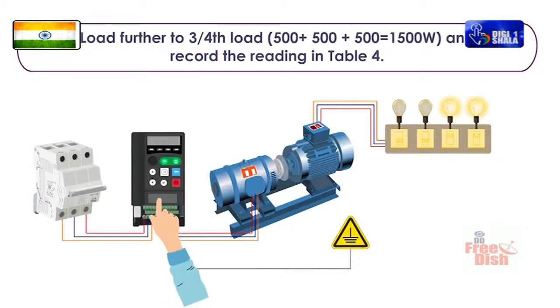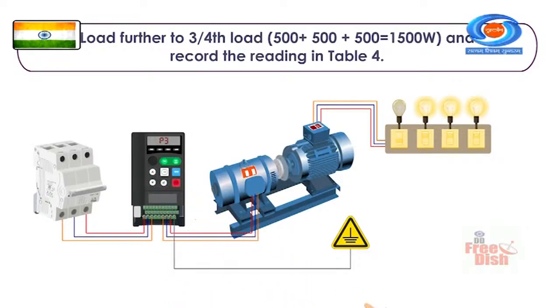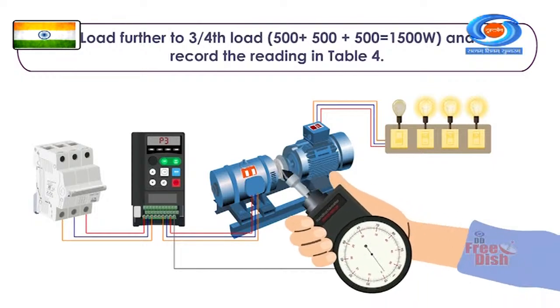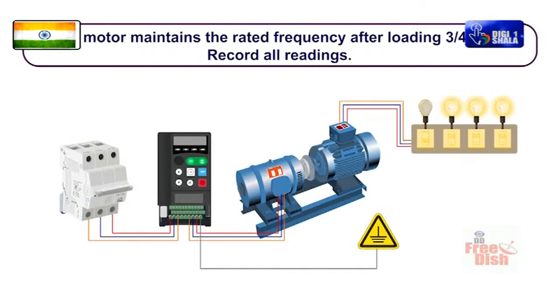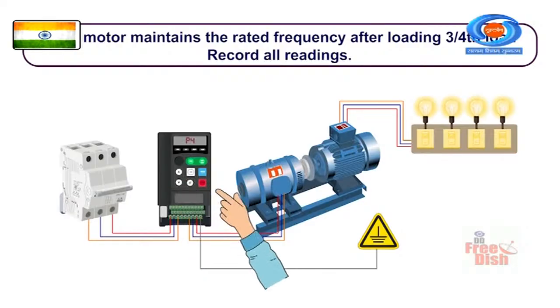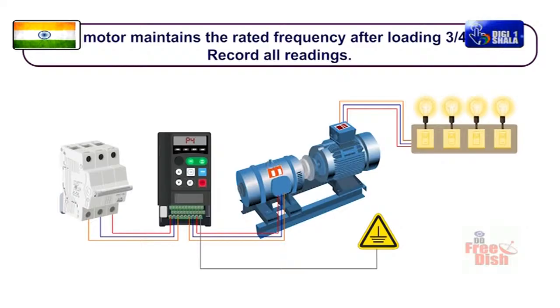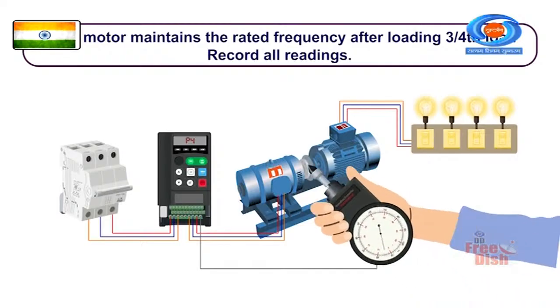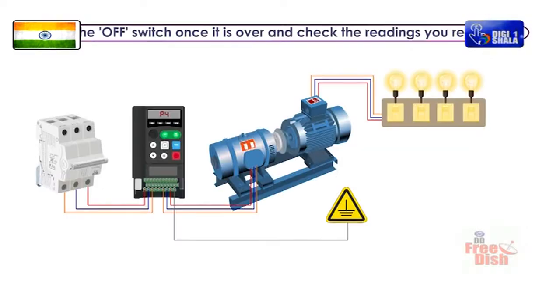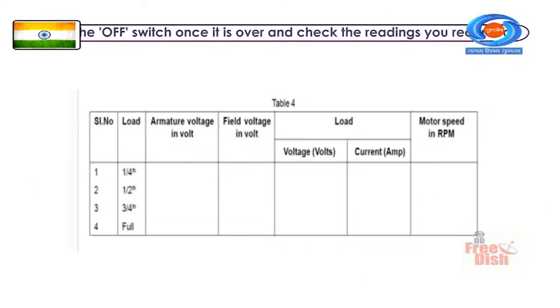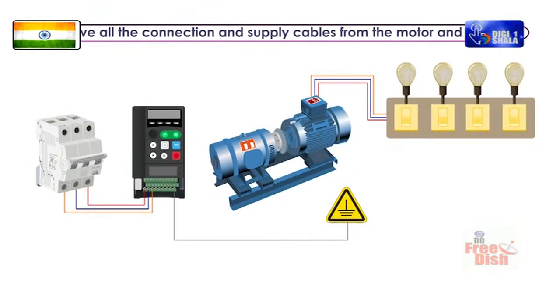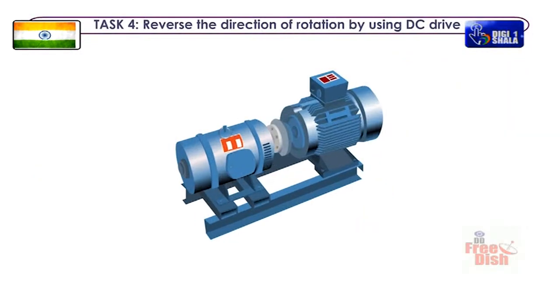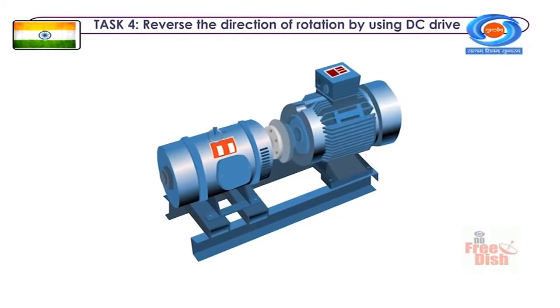Load further to 3/4 load, 500 plus 500 plus 500, which equals 1500 watt, and record the readings in Table 4. If the motor maintains the rated frequency after loading to 3/4 load, record all readings. Press the off switch once it is over and check the readings you recorded. Remove all the connection and supply cables from the motor and supply. Record your observations.